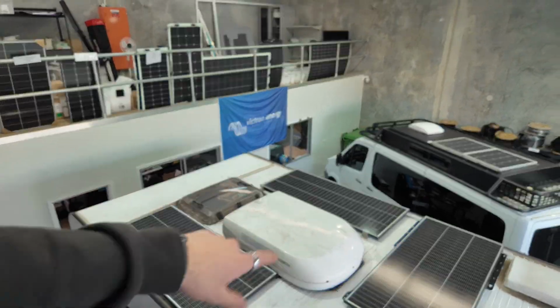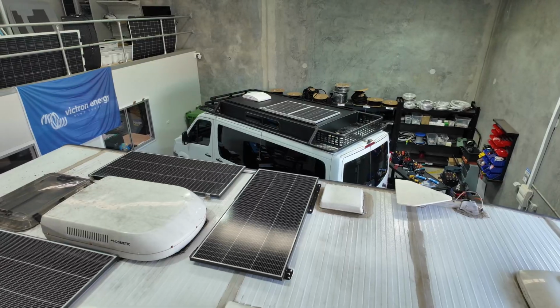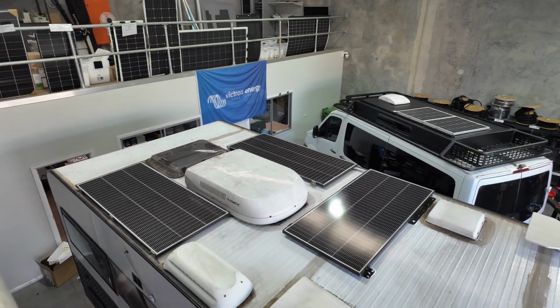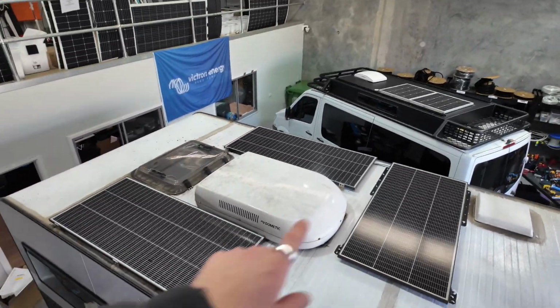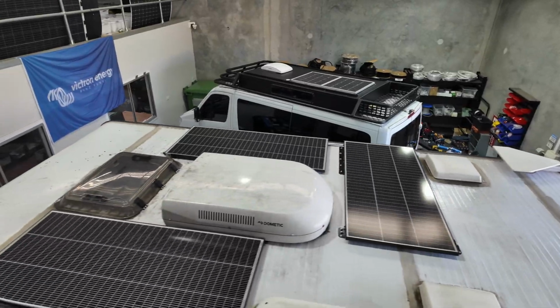So I recommended to the customer that these panels are not very good, old technology, and for the same size panel, you've gone from a 170 watt to a 225 watt. We've added 3 to go 660 watts, running through the 50 amp solar MPPT, using the original brackets and new brackets for this one. So they've gone from 2 times 170 watt panels that weren't in any good condition, unfortunately, to now a 660 watt system.